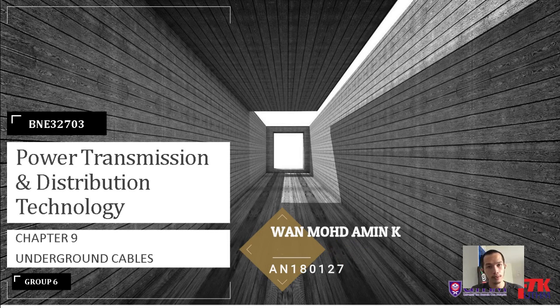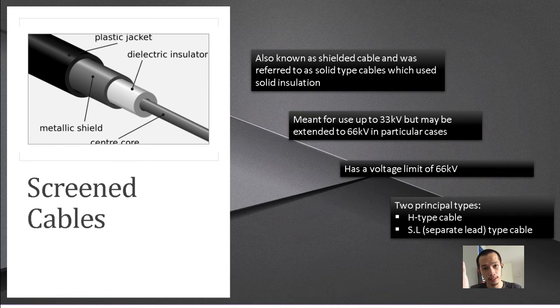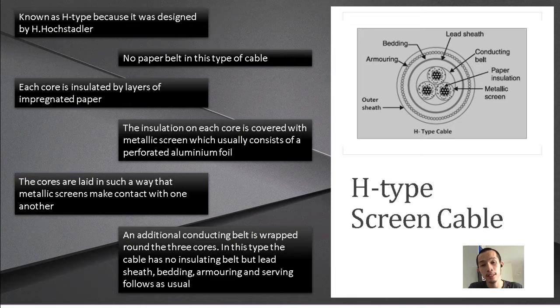This video from Group 6 will be briefing on the screen cables used as underground cables for power transmission and distribution. So screen cables, also known as shielded cable, and we refer to as solid type cables, which use solid insulation, are meant for use up to 33 kilovolts but may be extended to up to 66 kilovolts in particular cases. It has a voltage limit of 66 kilovolts with two principal types, which are H-type cable and also SL-type cable, separate lead type cable.